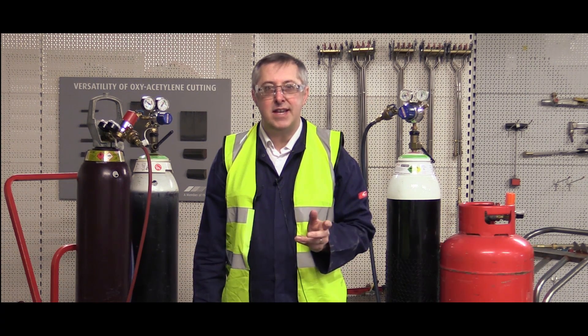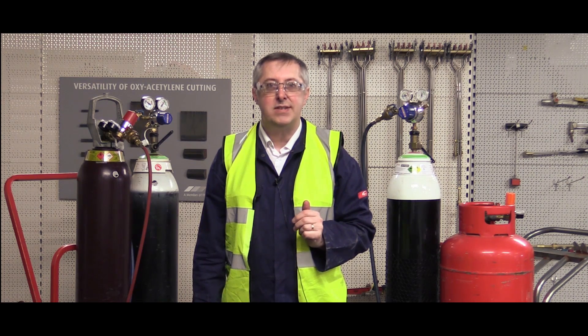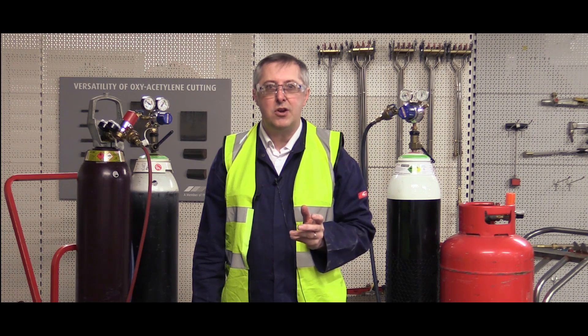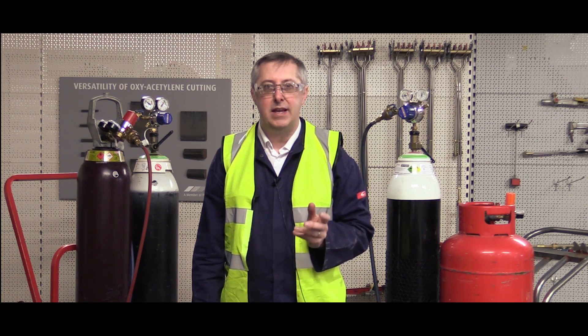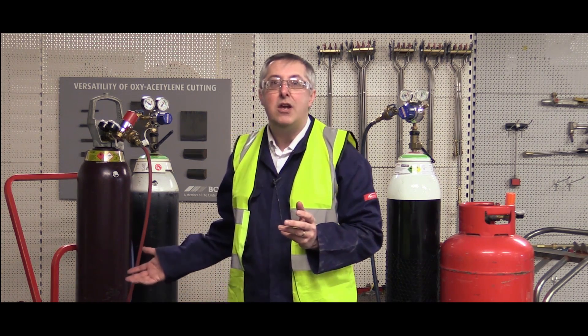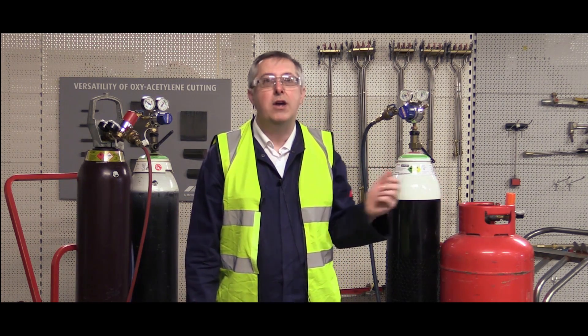Firstly, some facts about dissolved acetylene. Between 2003 and the end of 2012, the UK Fire and Rescue Service operated a significantly excessive and very disruptive protocol for dealing with fires involving acetylene cylinders. This original protocol caused much misinformation to circulate about the behavior of acetylene in response to fire, and in turn influenced the Health and Safety Executive and many ancillary bodies such as insurers to recommend that oxyacetylene should be replaced by oxypropane where possible.